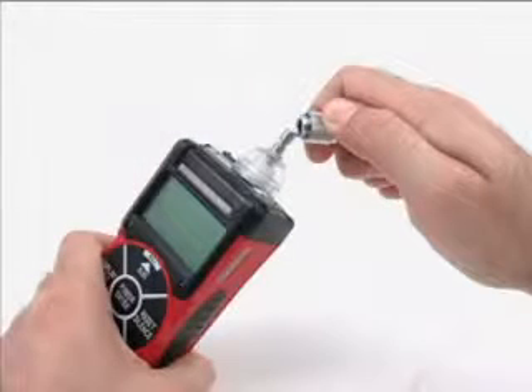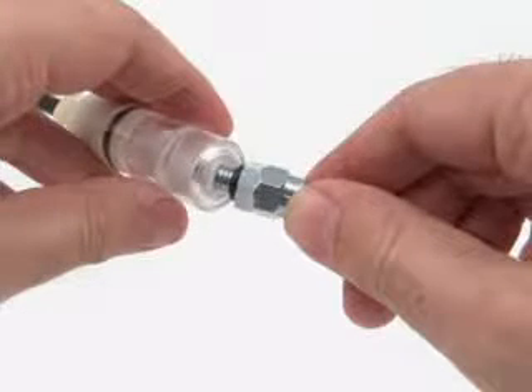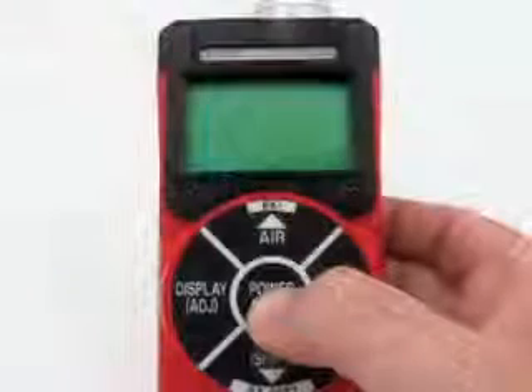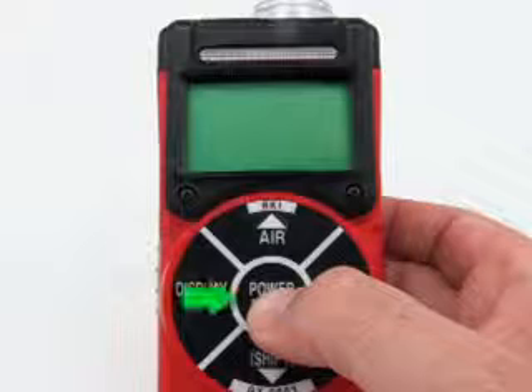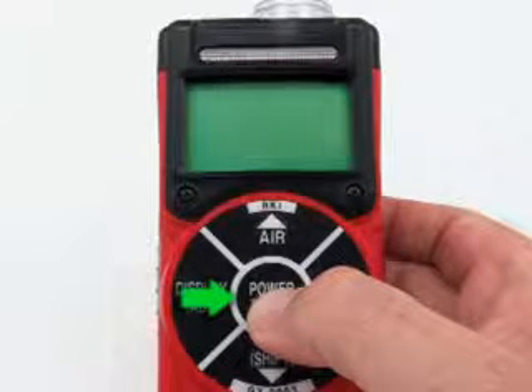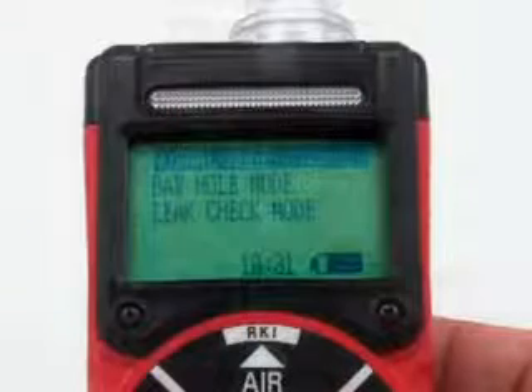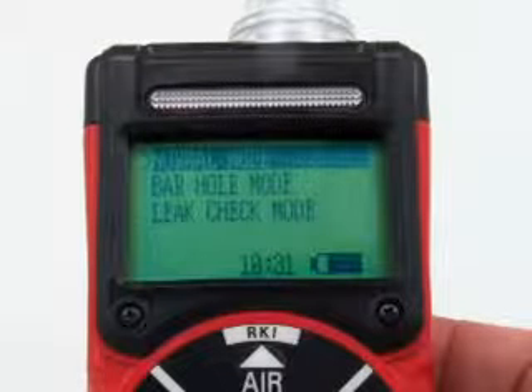To prepare for operation, connect the sample hose to the GX2003's Quick Connect inlet fitting. Next, screw the bar hole probe onto the sample hose's threaded fitting. To start the GX2003, press and briefly hold down the Power Enter button. The Mode Select screen displays.